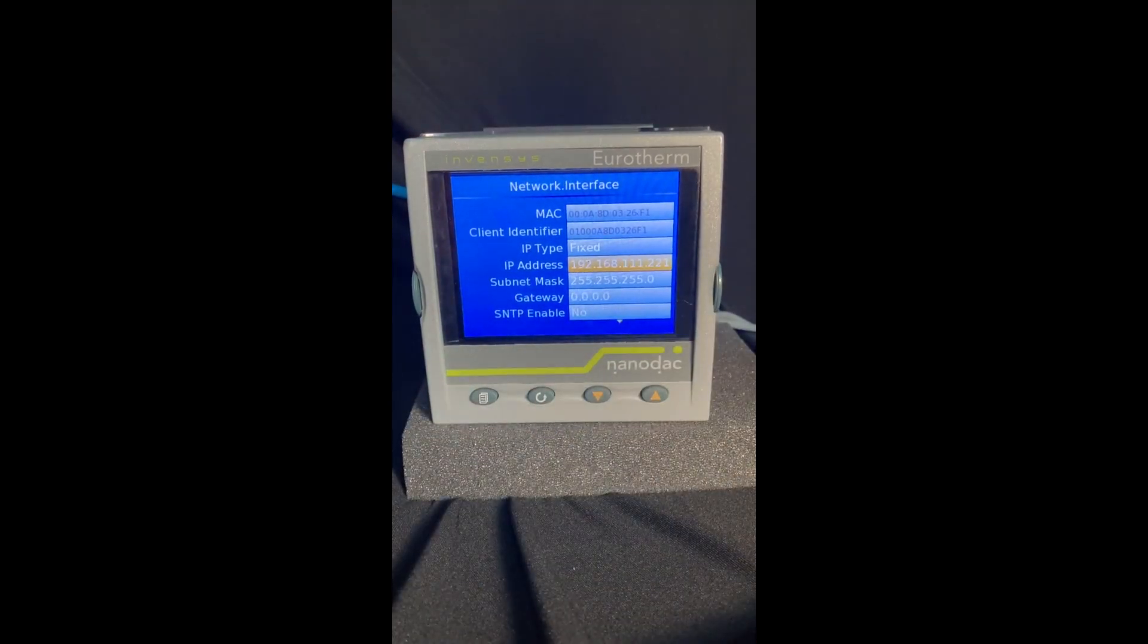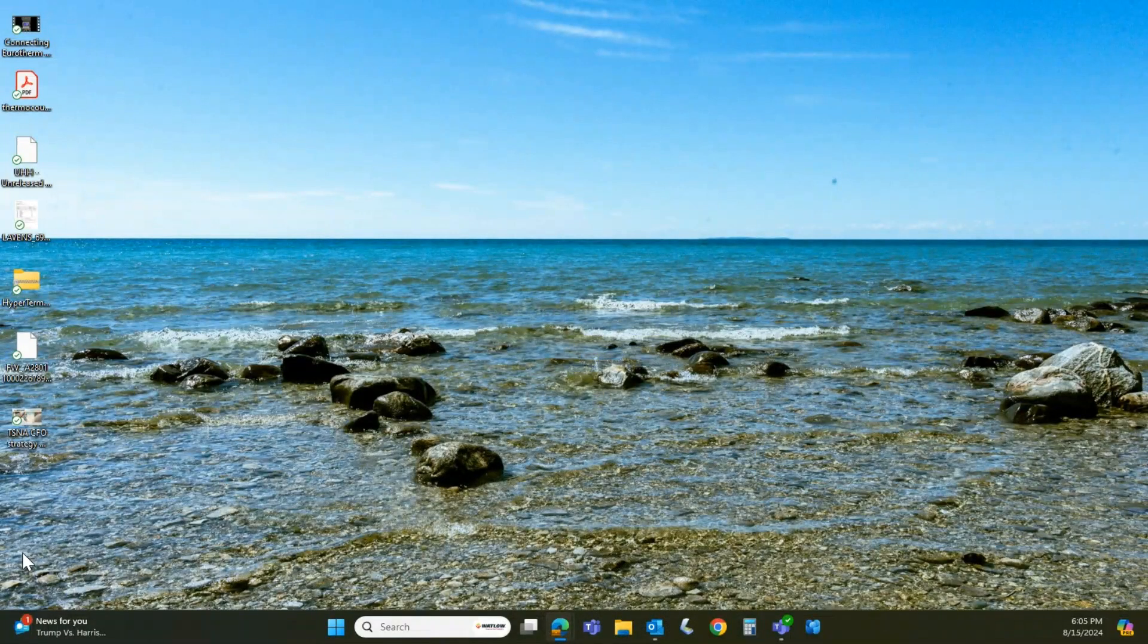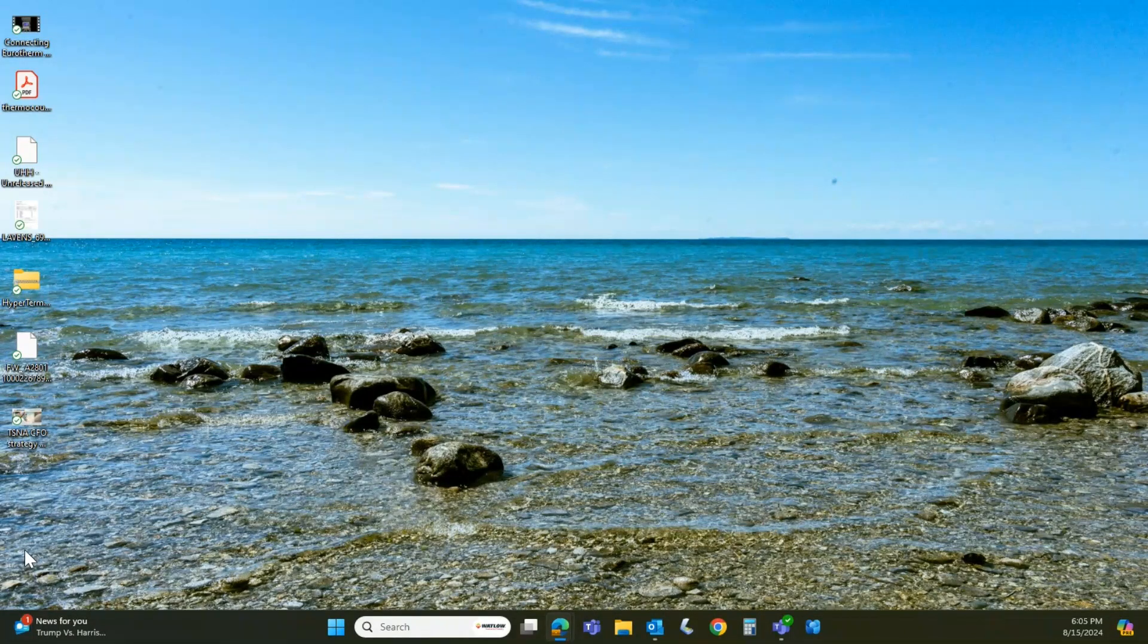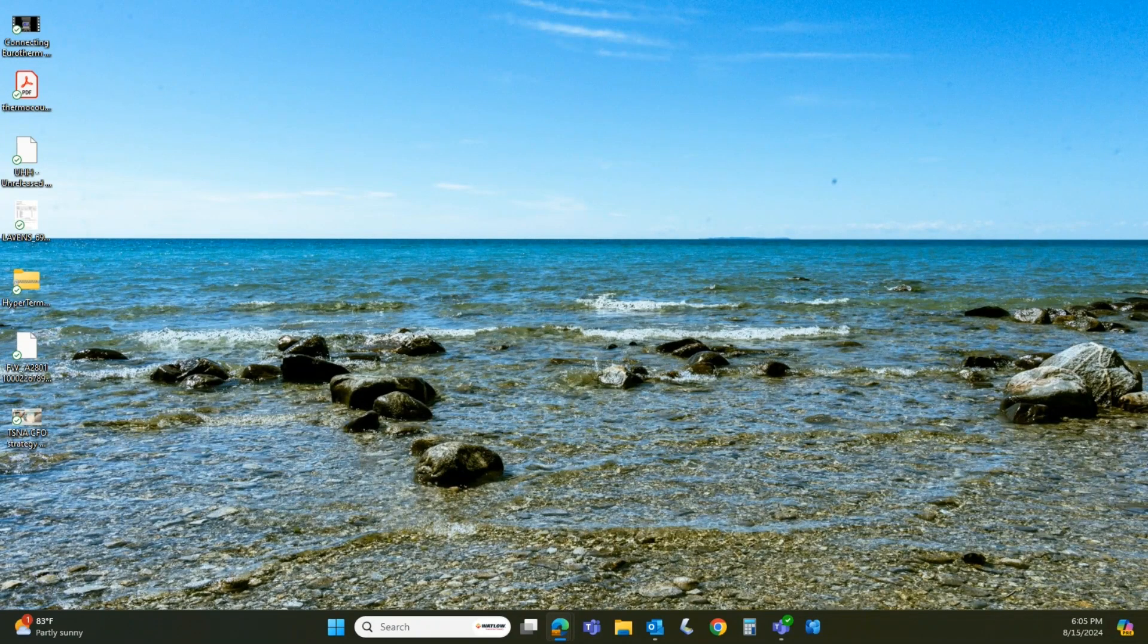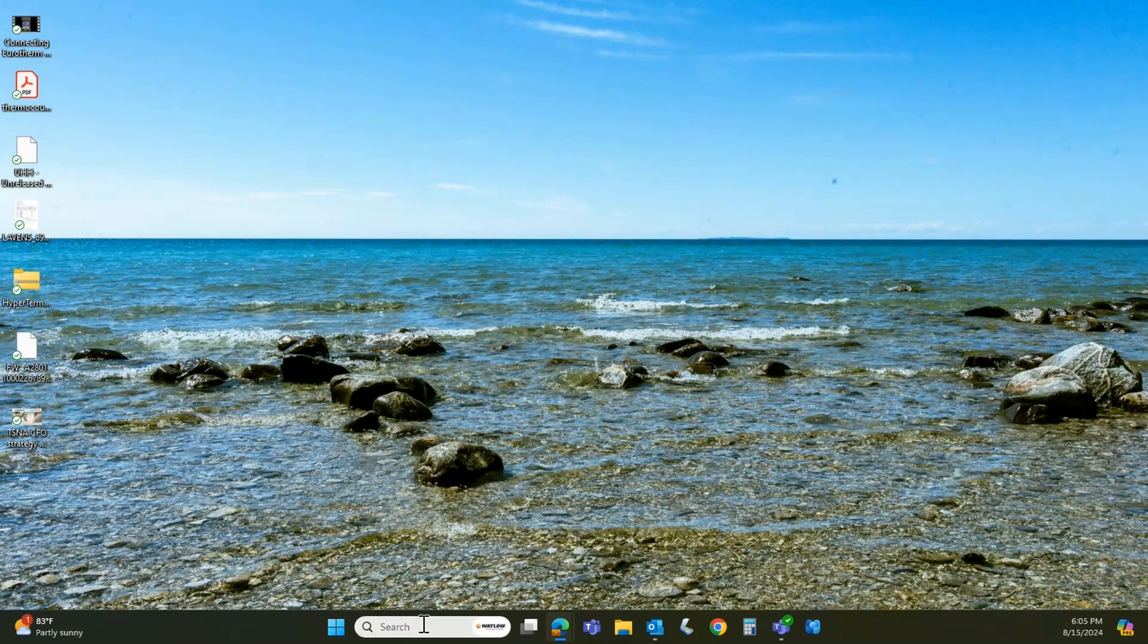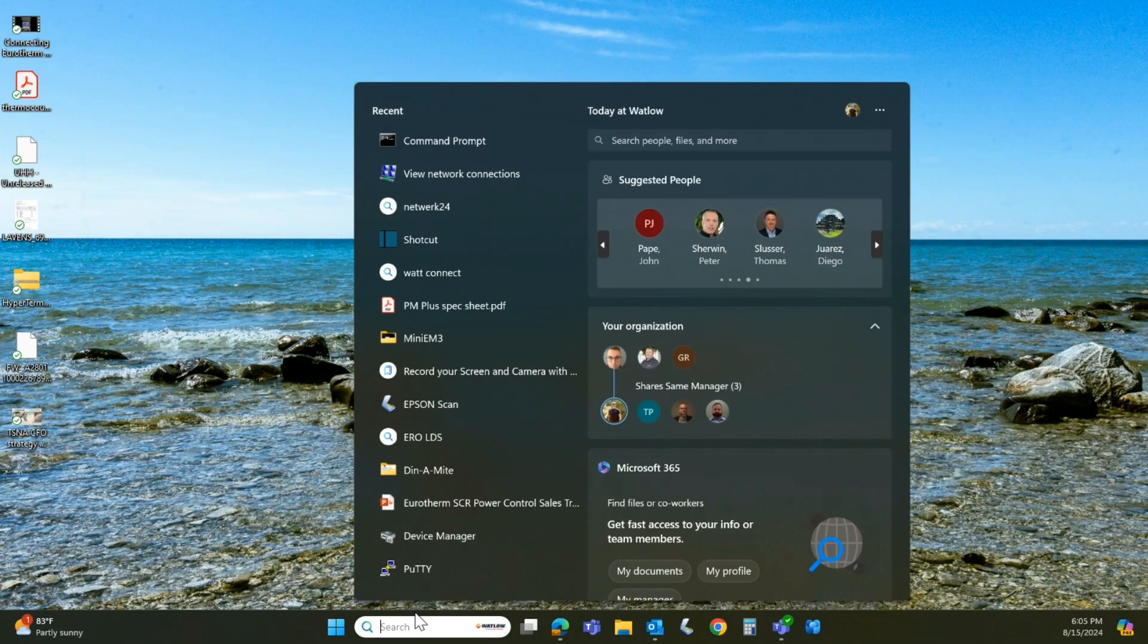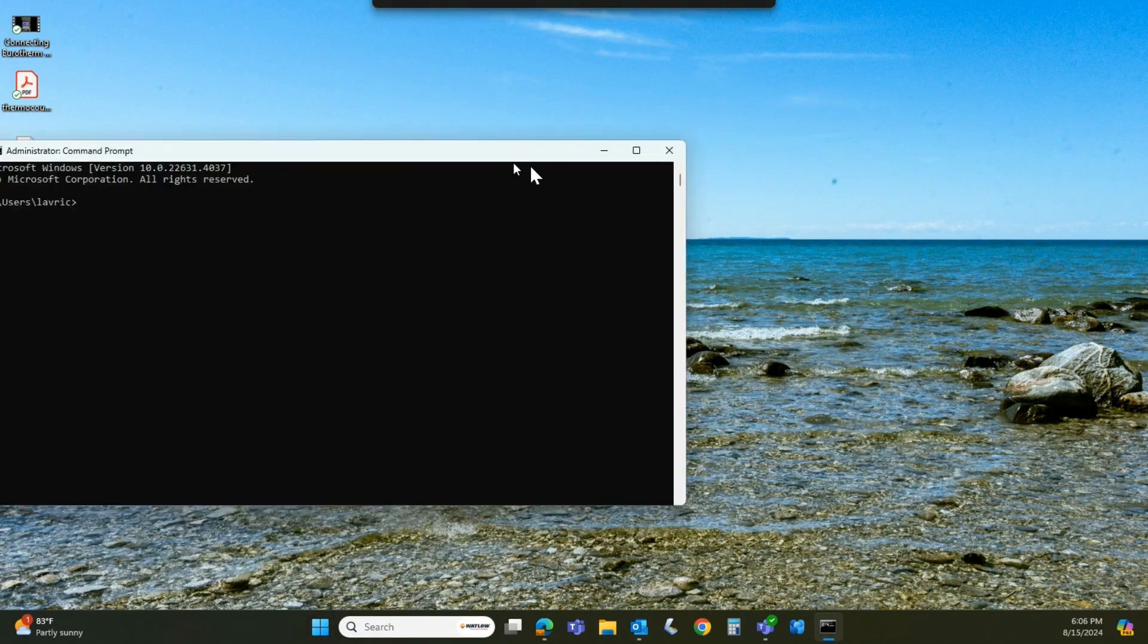So I'm going to pop back to iTools. All right, so what I usually do is the instrument address that we just put in has to be in the same sequence as your laptop's IP address, except for that last field. So what I usually do just to make sure communications are working is I come into my search bar and I type CMD, which is command and that's the command prompt.